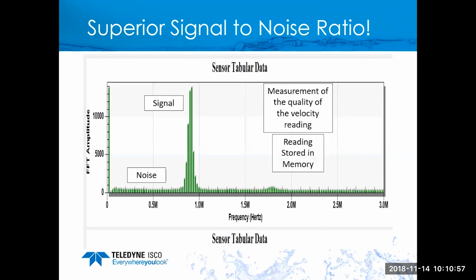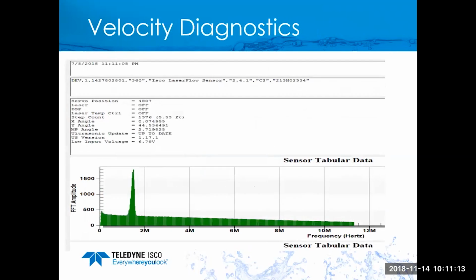This is stored again as Doppler power, and for Doppler power we need a minimum of 1,000 as a reading. So you can graph your level and velocity and flow, as well as Doppler power. You can pick out a point and say, yep, my reading was good, and here's why. So there's some really good diagnostic information available.